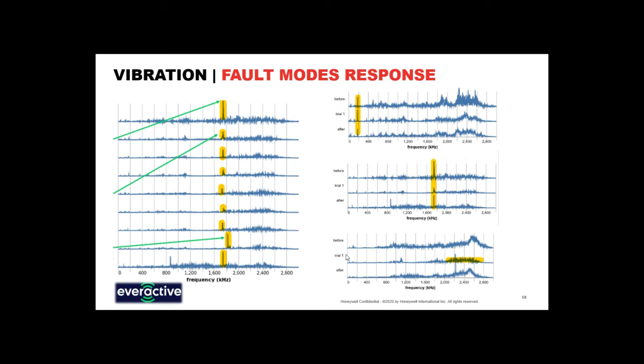It's obvious on the top and mid traces on the right hand side, it's just the peak of the output from the accelerometer. If you look at the bottom trend, that's getting to be somewhat challenging in terms of being able to clearly state that the sensor is capable of detecting an issue, a problem, a potential fail. So we had some interesting time with this. We found it's also a function of flow rate, but even so, good results.